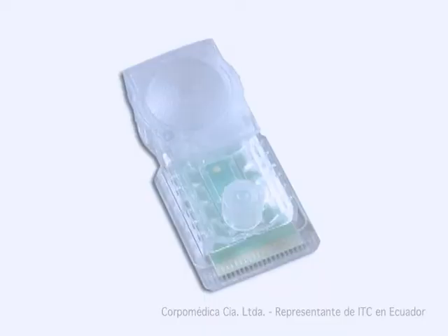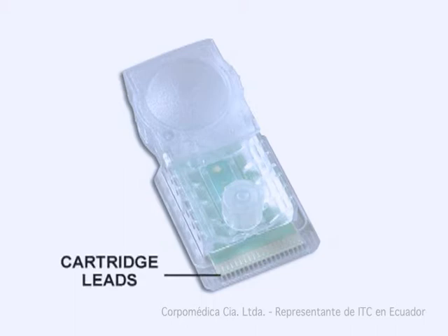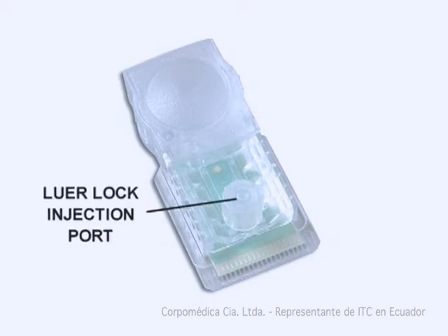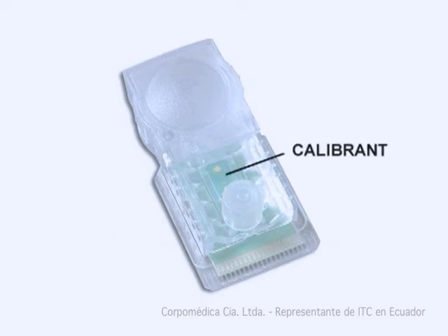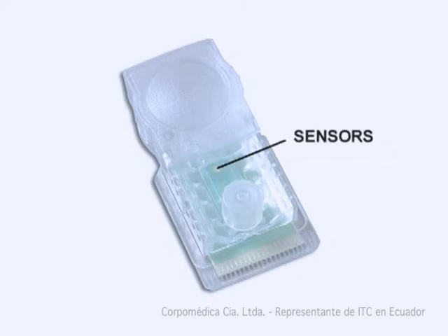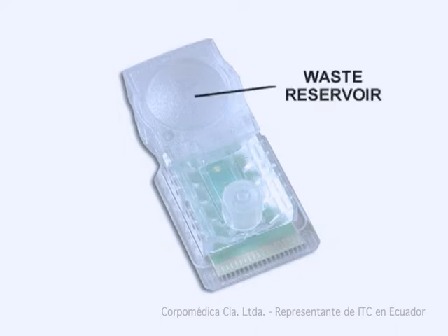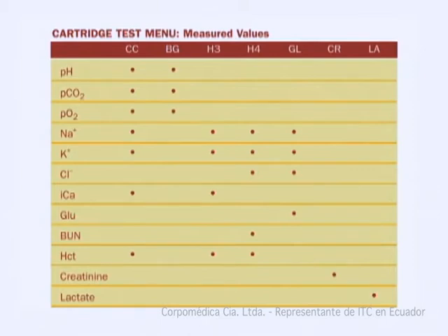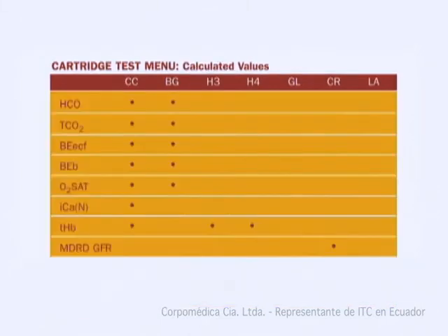Each cartridge contains cartridge leads, which electronically connect the cartridge to the analyzer; a Luer-Lock injection port, which forms a closed system and reduces biohazards; a calibrant, which covers and calibrates the sensors; and sensors, which measure analyte concentrations and calculate additional parameters. The waste reservoir safely holds up to 5 milliliters of sample and helps prevent cartridge overflow and spills. The IRMA TruPoint test menu consists of analytes that are available in a variety of panel configurations.